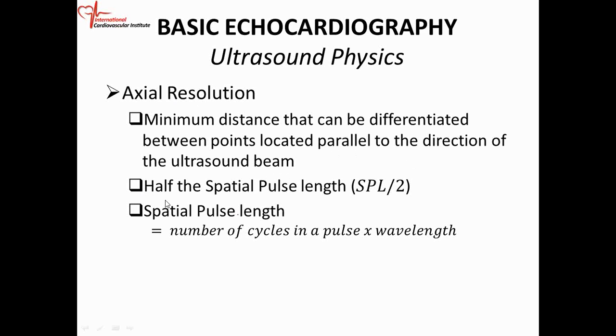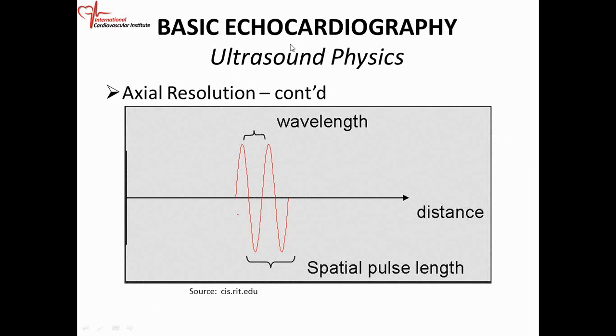And then there's something named the spatial pulse length, and we'll go over that. The axial resolution is half of the spatial pulse length. The spatial pulse length is basically the number of cycles in a pulse times the wavelength. Let me explain that a little more, because they might ask you, what is the axial resolution? And they will give you a pulse. So you need to know that it is the spatial pulse length divided by 2. So remember what a pulse looks like.